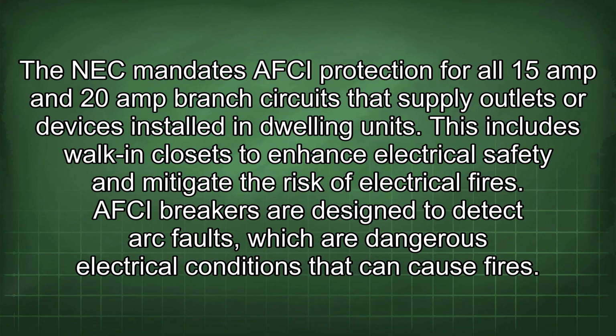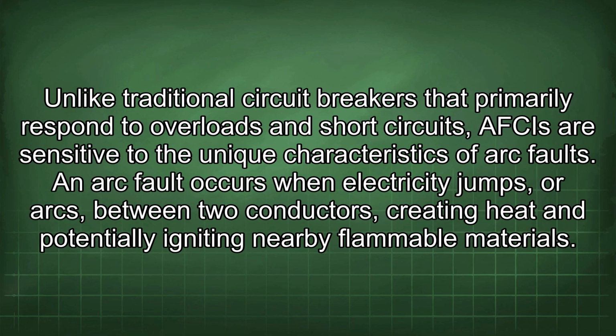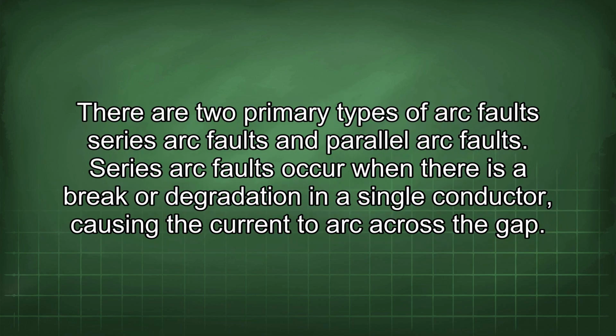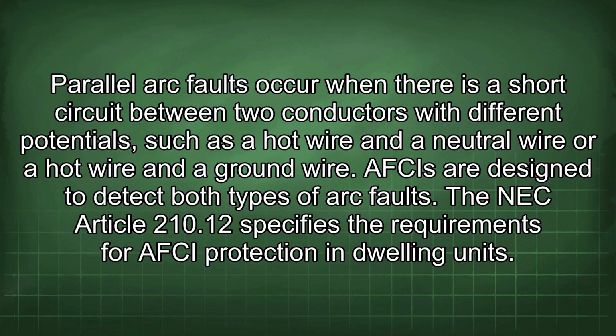AFCI breakers are designed to detect arc faults, which are dangerous electrical conditions that can cause fires. Unlike traditional circuit breakers that primarily respond to overloads and short circuits, AFCIs are sensitive to the unique characteristics of arc faults. An arc fault occurs when electricity jumps, or arcs, between two conductors, creating heat and potentially igniting nearby flammable materials. There are two primary types of arc faults: series arc faults and parallel arc faults. Series arc faults occur when there is a break or degradation in a single conductor, causing the current to arc across the gap. Parallel arc faults occur when there is a short circuit between two conductors with different potentials, such as a hot wire and a neutral wire, or a hot wire and a ground wire. AFCIs are designed to detect both types of arc faults.